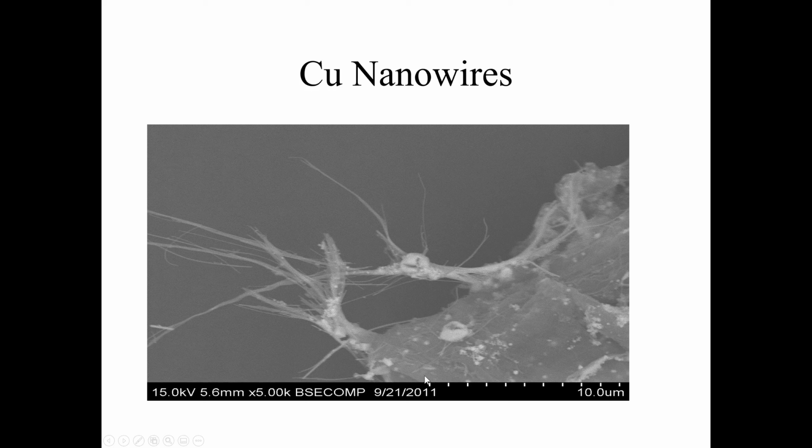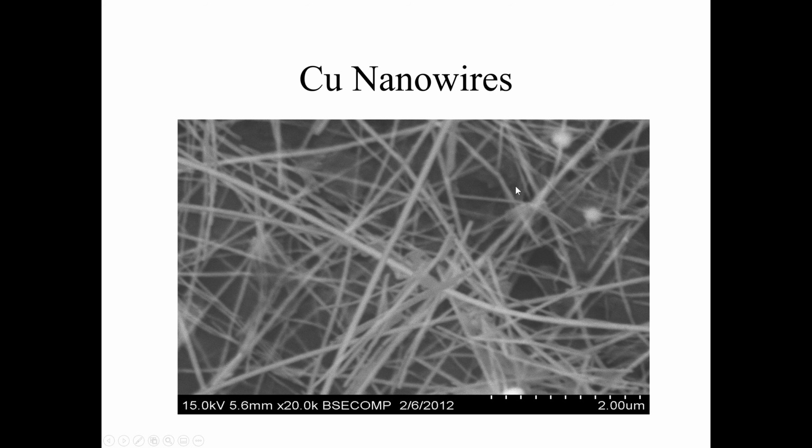This whole section is 10 millionths of a meter. So these are pretty small. These are the nanowires at even a higher magnification. Again, you may be asking, why is it a little fuzzy? It's because, number one, vibration. Not all these fibers are physically attached to the sticky carbon tape, so they move around under high vacuum. You get magnetic field interference, RF noise, people walking down the hallway, truck rumbling down the road.